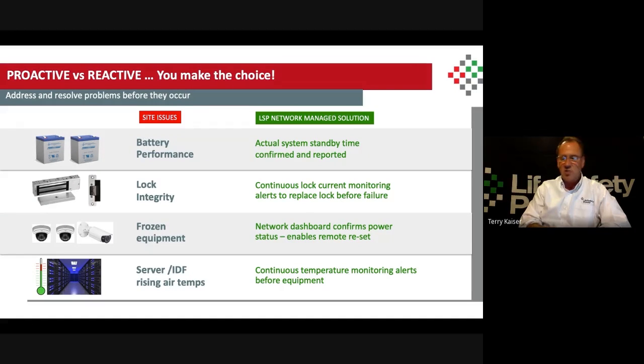I can set a schedule to reoccur every 90 days, every 100 days, whatever you set it for, to do a test on those 8 doors under load. I will physically drop AC power under load and deliver a test result. If it comes back below the recommended amount of time, it'll give you an email notification, so now I know it's time to replace those batteries.